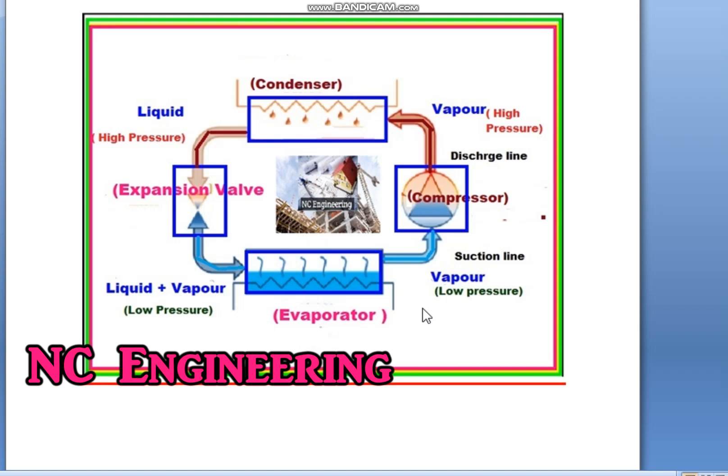Nowadays we are using a more common refrigerant — R410A — whose boiling temperature is approximately minus 48 degrees, which is also a very low temperature. So when the air comes in contact with the coil through which this refrigerant is passing, it will take heat from the air and convert to vapor, and the air will become cooler and pass inside the room as cold air. This low pressure vapor again goes to the suction of the compressor and the next cycle starts.